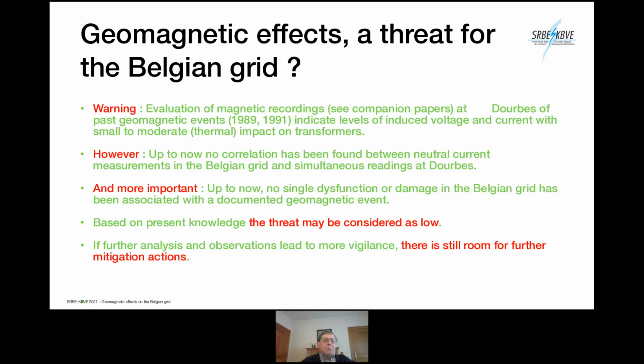So, from our point of view, we can consider that the threat is rather low. Now, if further analysis shows that we should do anything or we need to have more vigilance, then there is still room in Belgium for further mitigation actions. For instance, we can actively manage the neutral point resistance. For the moment, it's not a case.